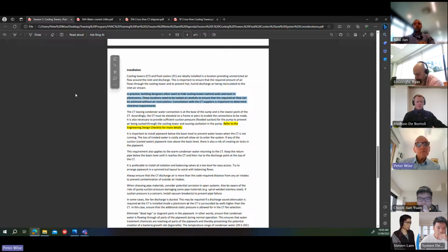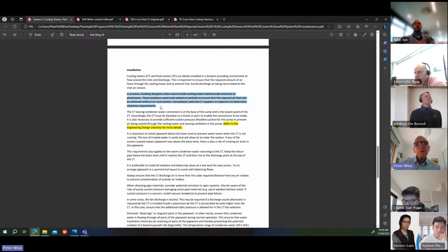What you'll find in practice is building designers and architects often want to hide cooling towers behind walls and even in plant rooms. You'll find this happens quite a lot. These locations need to be looked at very carefully to ensure that the required airflow can be achieved without air recirculation.